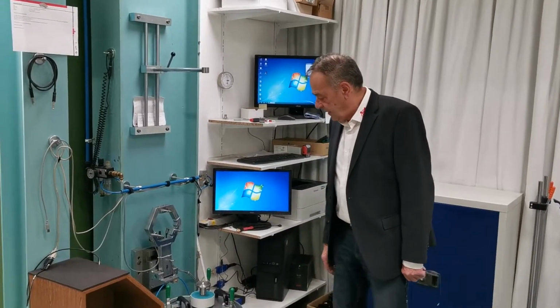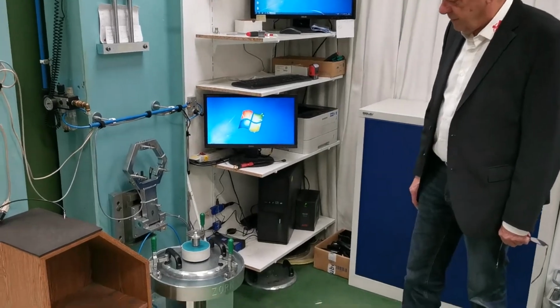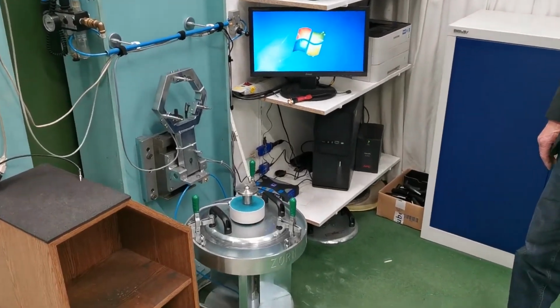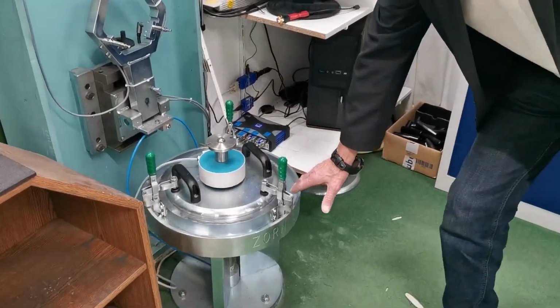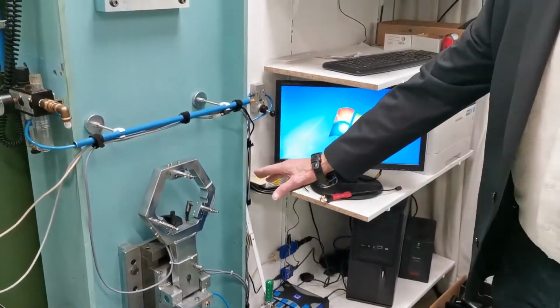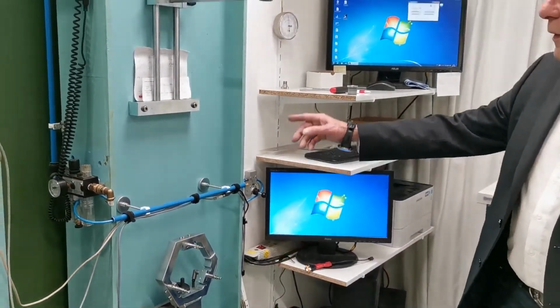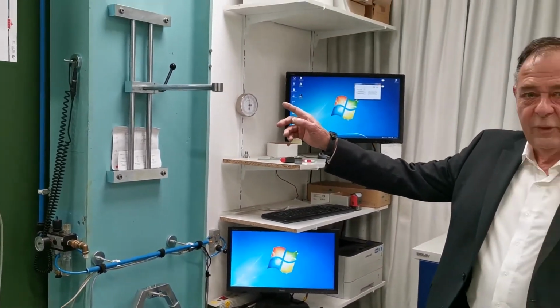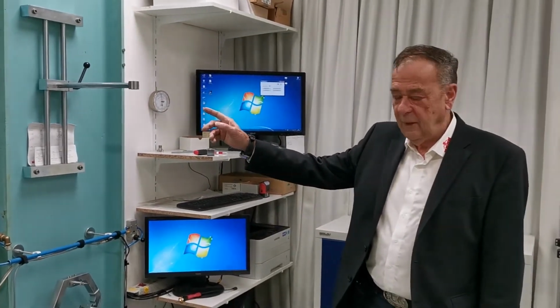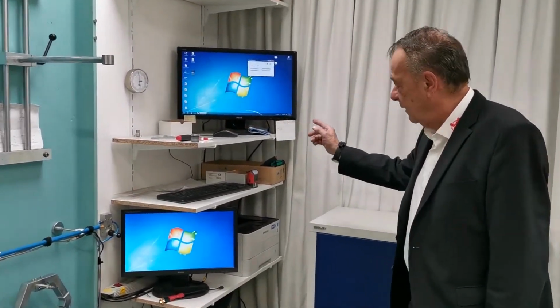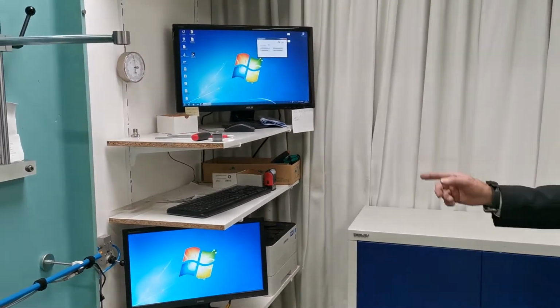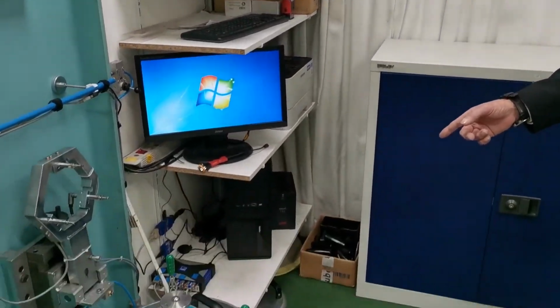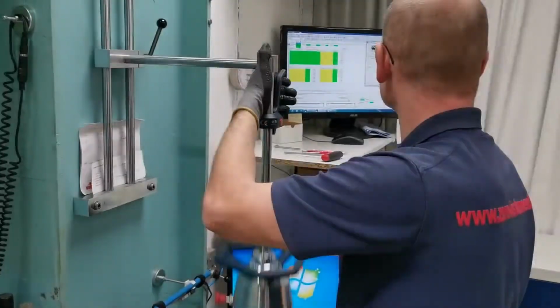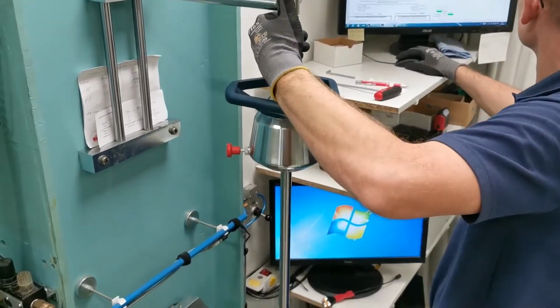This is the ZORN Instruments LWD calibration stand. The stand basically consists of these 5 components: a solid steel pedestal, a foldable bridge for 3 displacement transducers, a holding device for the guide rod. In the background, you see a computer with 2 screens and a measuring amplifier. Now, what happens exactly during a calibration?